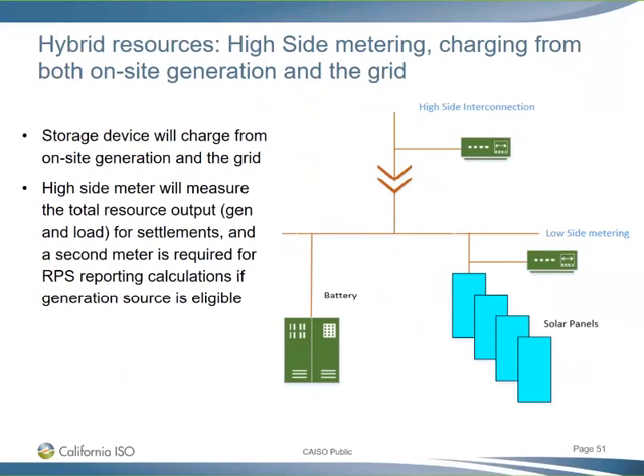But on the battery side, having a meter there would be important for confirming the round-trip efficiency losses of the battery, so you're not just relying on the battery management system, but also on the meter that reflects the energy going in and coming out of the battery, whereas you don't need that flexibility on the solar side. That was one iteration of the metering scheme not shown here, and I think the one that makes the most sense to capture all the relevant information.